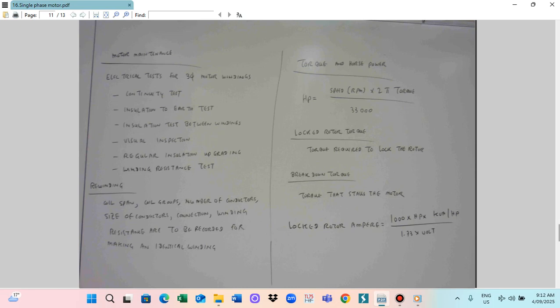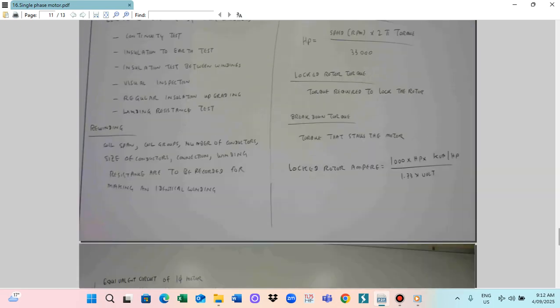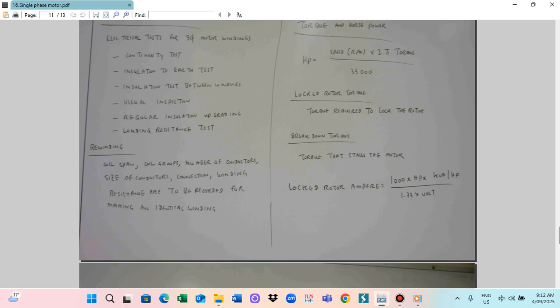Another important thing is the motor slot. Before you put in the winding, you have to put in the insulation. This insulation should be of appropriate cover. The height of the insulation is very important. Sometimes this height is too short. What happens is that when you put in the winding, the insulation originally looks like here, but afterwards it will be like this. So this is the gap.